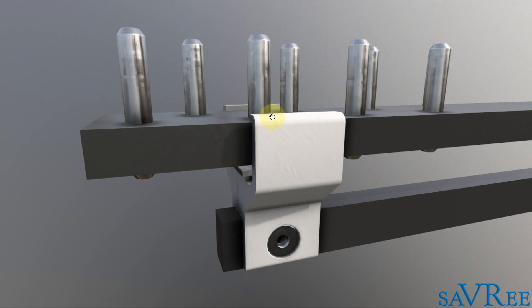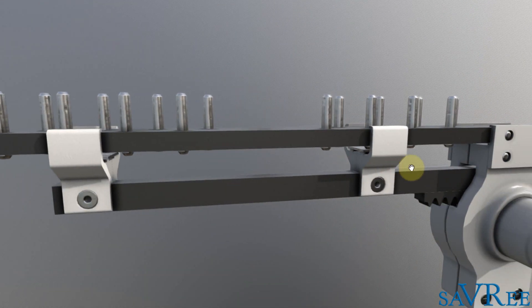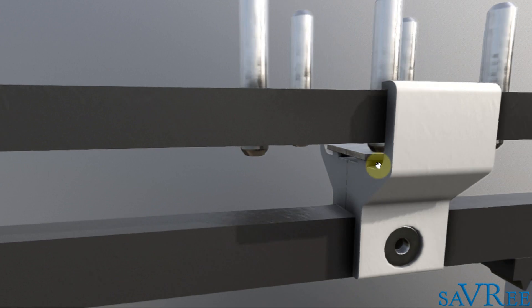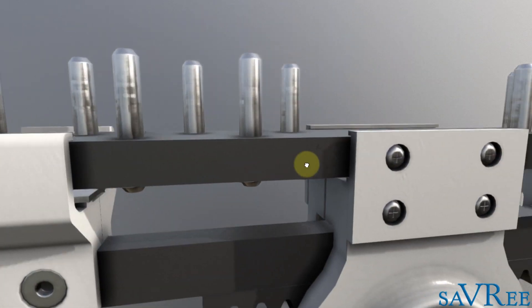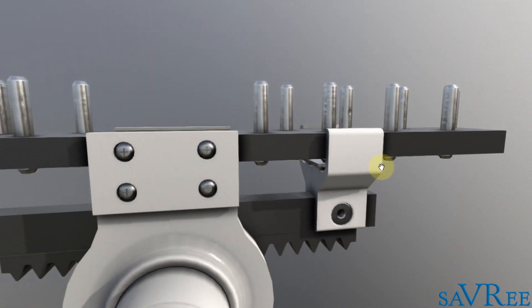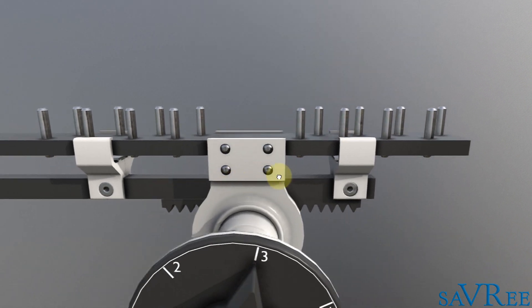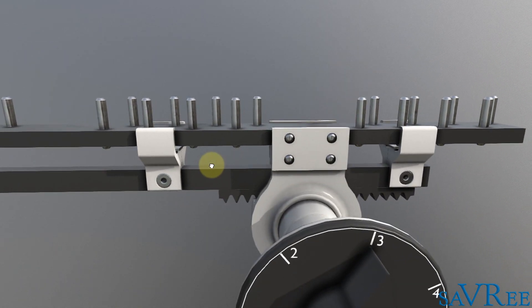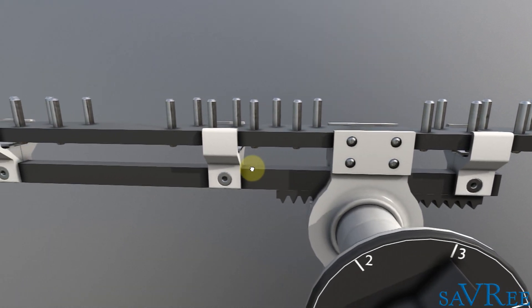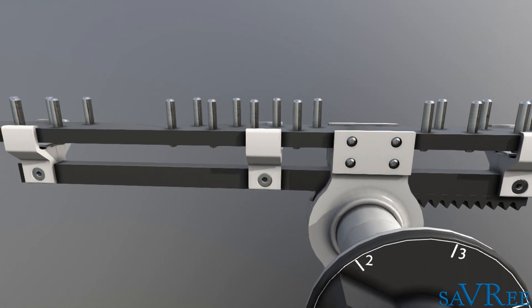Now each of these pins are connected to windings on a transformer, and as it's sliding along the pins, we can see it's also doing it here on this connection and also here on this connection. In a three-phase transformer, each of these pins are associated with a single phase on an electrical transformer, and as it's moving it's actually changing the turns ratio on the windings of the transformer.